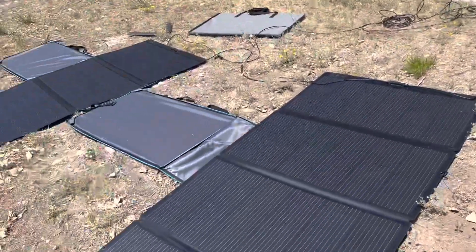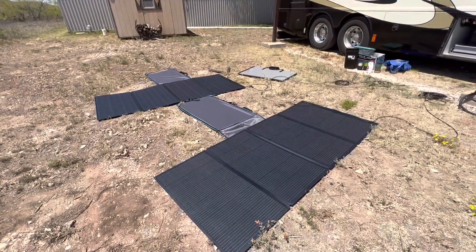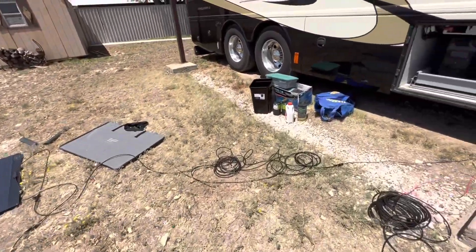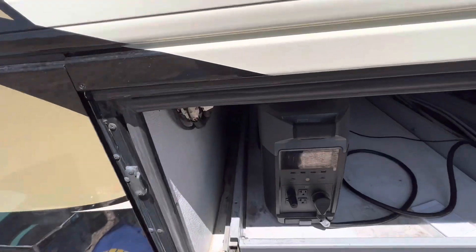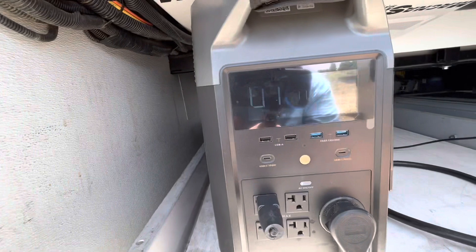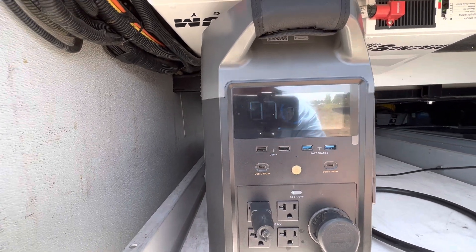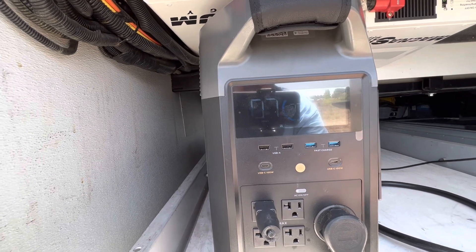Alright, so we have two 400-watt panels tied in series, and now I'm not sure if you're going to be able to see it but I'll get you a picture. What we have is 569 watts coming in, 867 watts going out. However, we have increased our run time by — probably about another three hours — we've got seven hours there now.